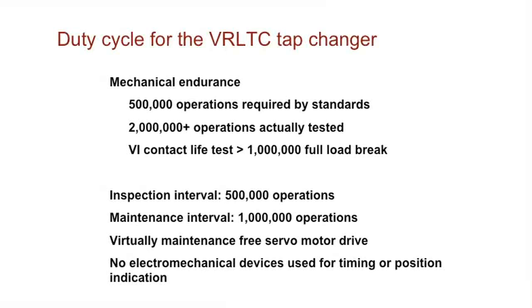Up here is where the arcing goes on with your vacuum interrupter. What that does is that interrupter, as soon as that starts to go on position, it switches it out here in the bypass. The bypass opens, the vacuum takes the current going into the next position. So all that arcing and everything is happening in that vacuum compartment, which reduces your contact wear and tear.